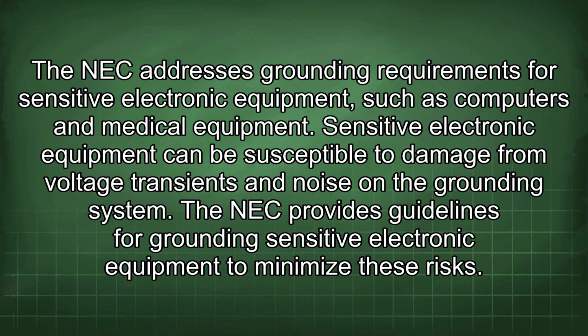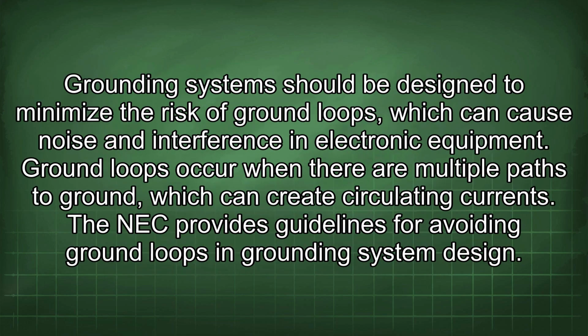Sensitive electronic equipment can be susceptible to damage from voltage transients and noise on the grounding system. The NEC provides guidelines for grounding sensitive electronic equipment to minimize these risks. Grounding systems should be designed to minimize the risk of ground loops, which can cause noise and interference in electronic equipment. Ground loops occur when there are multiple paths to ground, which can create circulating currents. The NEC provides guidelines for avoiding ground loops in grounding system design.